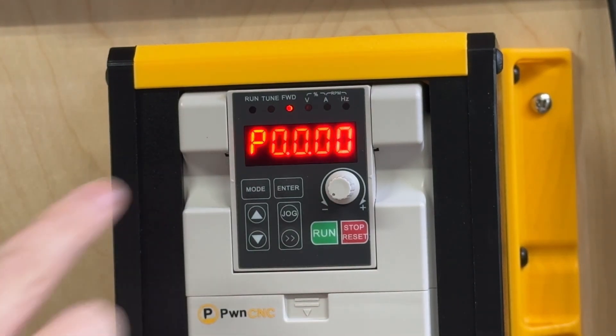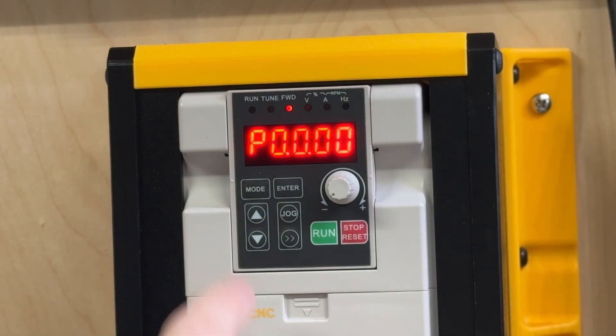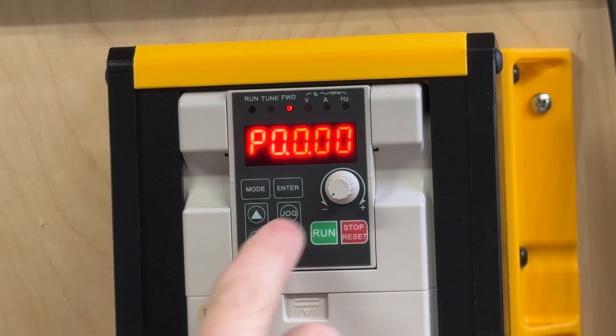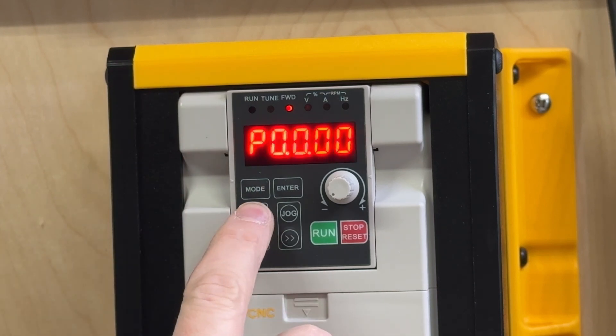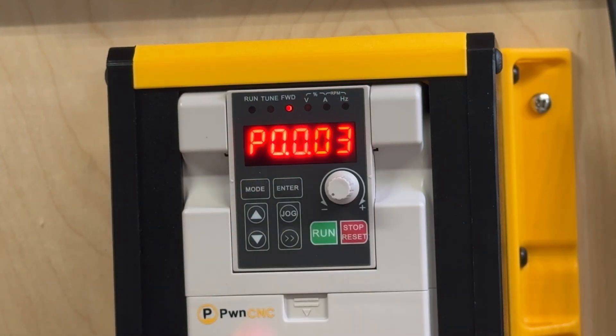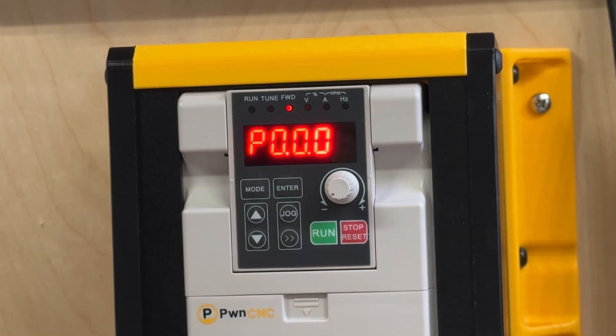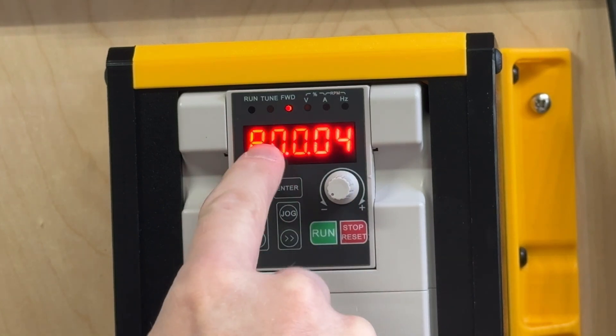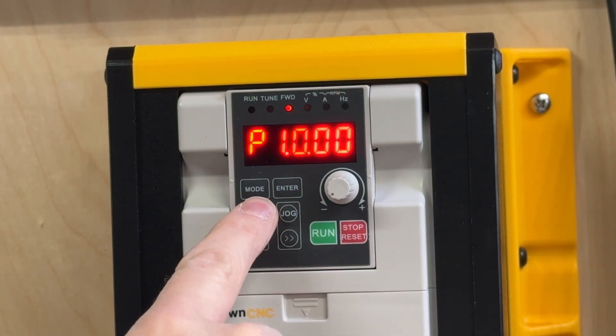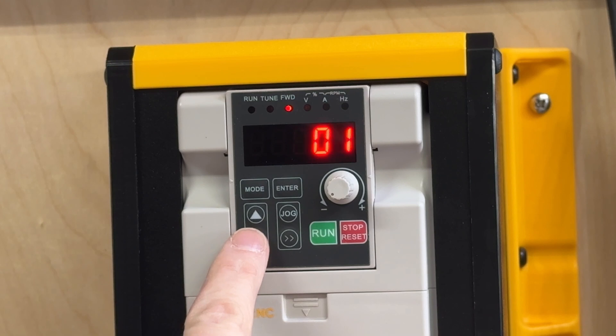When you first hit mode, more than likely you're going to pop up at P0.0.00. You're going to use the up and down arrows, the double arrow, and the enter key to navigate. The first code we need to change is P0.0.04 — hit enter and change that to a 1 by hitting the up arrow, then hit enter. The second code: hit the double arrow to move to the first digit, change it to a 2, so P2.0.00, hit enter, and change that to a 0.